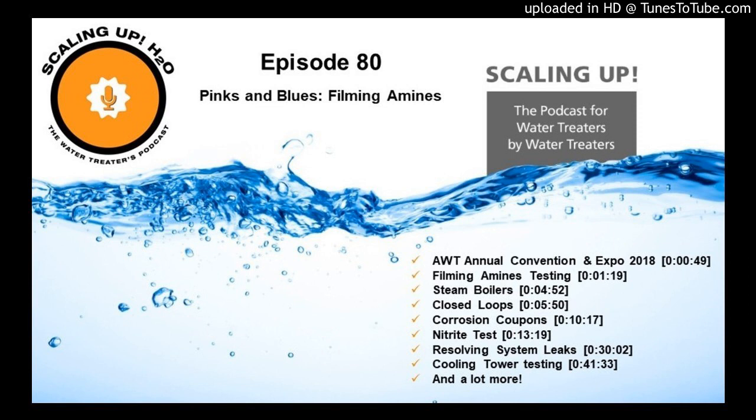And here is one of the very few axioms that we have in the water treatment industry. Are you ready for this? Here it comes right at you from my lips, through the airwaves, into your speaker, through your ears. 1 pound of anything in 1,000 gallons of water will yield 120 parts per million. You're thinking, well, a pound of what, Trace? Well, a pound of anything.